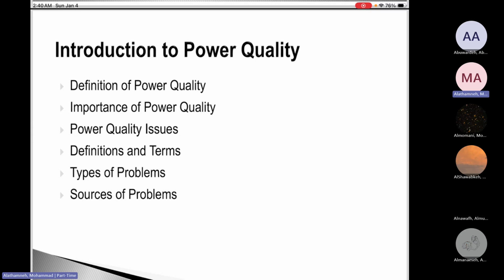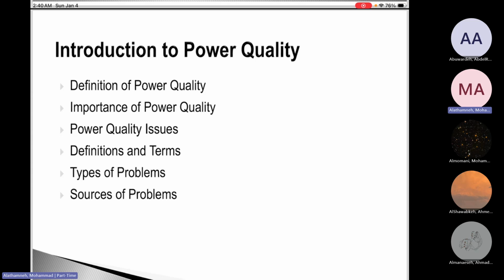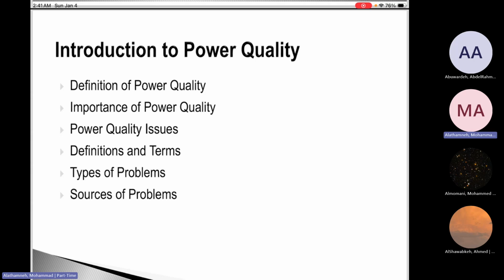We will also talk about the main sources of power quality problems: the supply side, the load side, or the interaction between them. It can be from the load side if you have nonlinear loads. It can be from the interaction between the load and the source when we have grid-connected systems, for example renewable energy, which is also supplying current or power. When we have a three-phase inverter, it can inject harmonics into the system as well. So the load can be a source of power quality problems, the source can be a source, and the interaction between them can be a source.